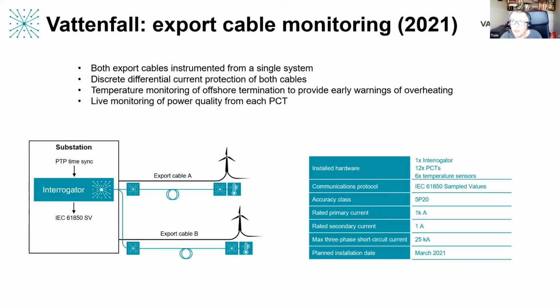There's just one point to jump in, to highlight how the first one you saw was for 33 kV, and this one up at Aberdeen Bay is on 66 kV, and it's the same sensors, the same technology, that can do both of these cables. Yep, and these are both retrofits as well. So it's easily attached to an existing wind farm, and of course a new install would work as well.